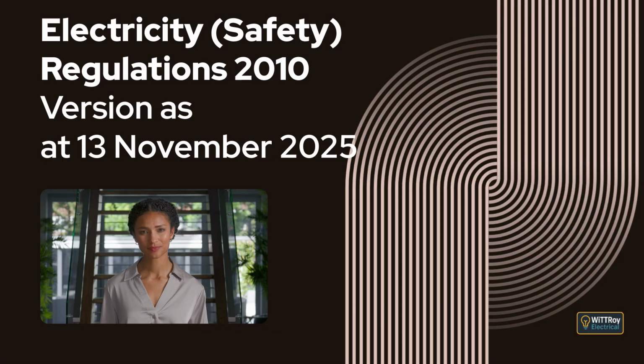It also explains that if an installation, other than low-voltage AC railway signaling equipment, is supplied with electricity from a main system of supply, the installation must have at least one main switchboard. It further explains that the switchboard located electrically closest to the point of supply must be a main switchboard. The regulation finishes by explaining that a person commits an offence and is liable to a Level 2 penalty if they connect an installation to a supply of electricity in a way that does not comply with this regulation.